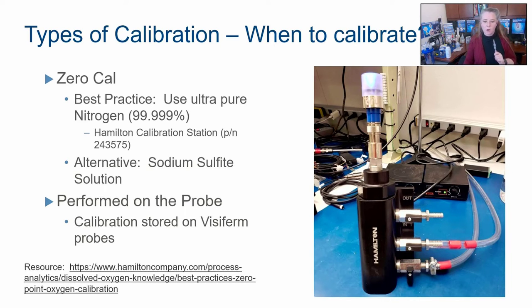It just depends on your facility and what they're going to do. I suspect if you're doing this at Laney, Doug will do it probably with the sodium sulfite just because it's easier. You want to make the sodium sulfite fresh every day because that solution will pick up oxygen and you don't want to calibrate in an oxygenated solution.